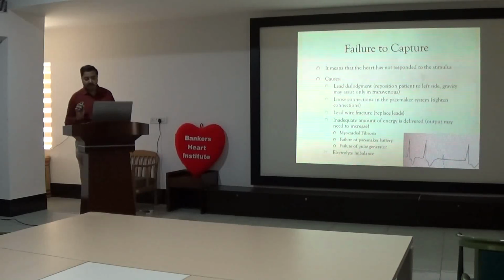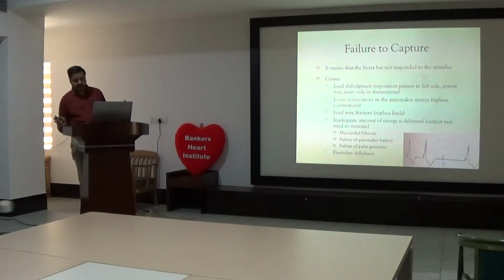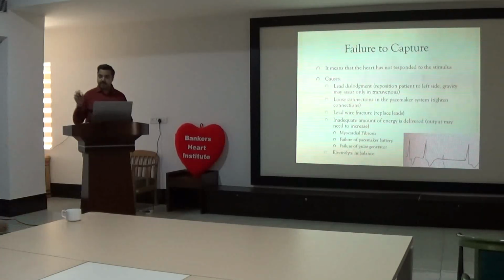So this stimulus has not been delivered to the heart. Causes would be multiple. Starting from the lead, either the lead is dislodged. Here it is not dislodged totally. Maybe it is moving inside the heart, and that's why this pacing spike is not delivered to the ventricle. So lead dislodgement is the first common cause. In case of transvenous temporary pacing, make the patient lie in the left lateral position, and with gravity the lead will fall down again onto the RV. It can work, but very rarely it doesn't work as such.